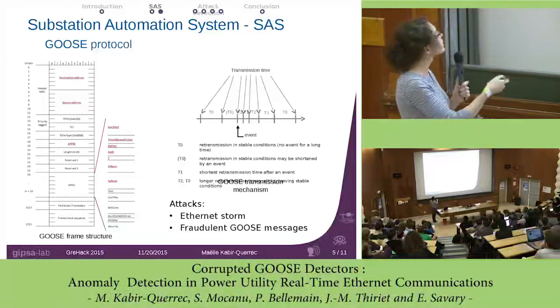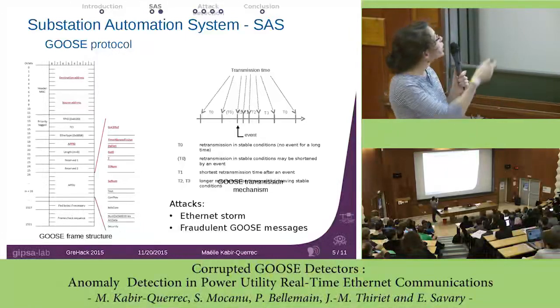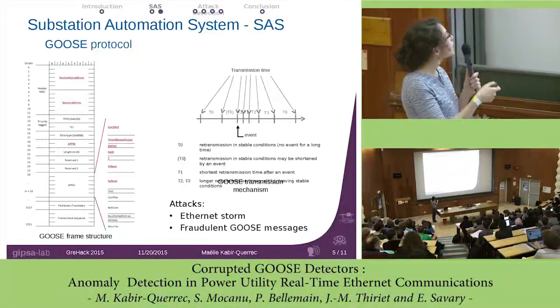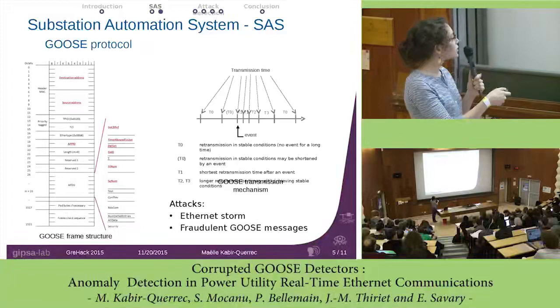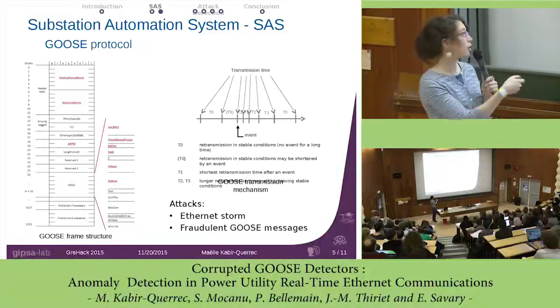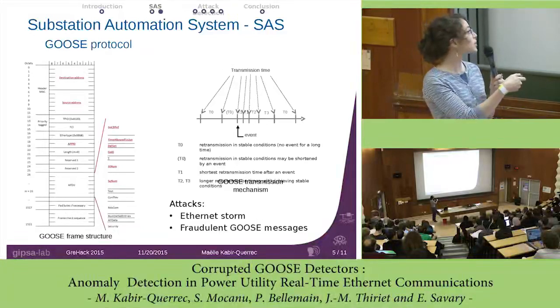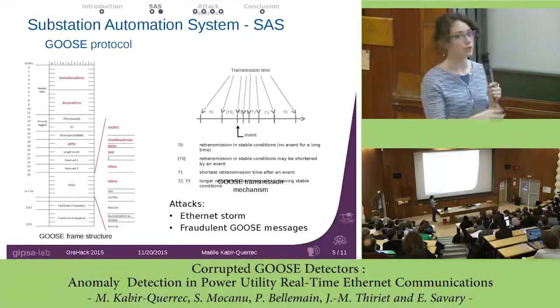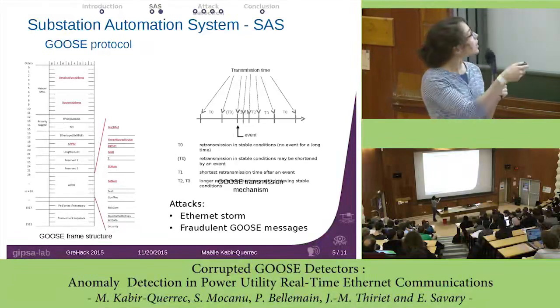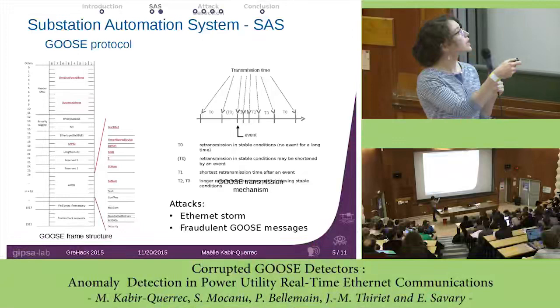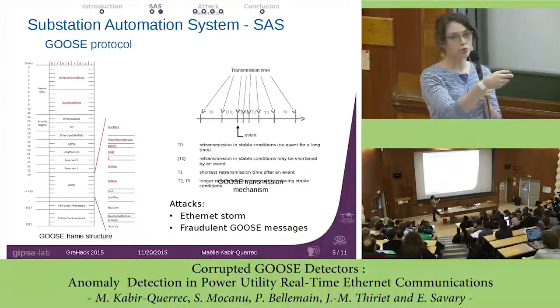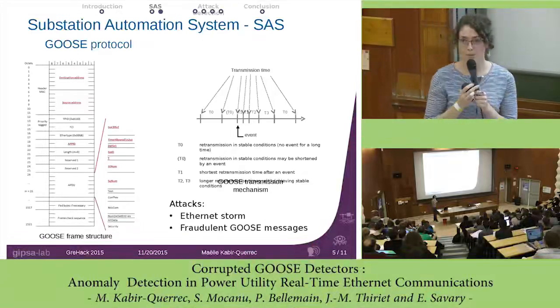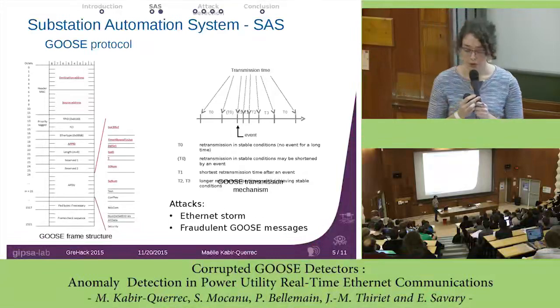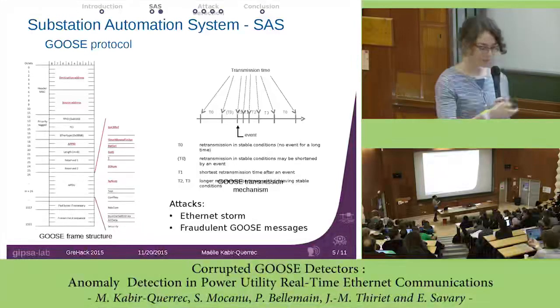So this is basically an Ethernet frame. You start your frame with destination address and source address. And the most interesting part is the PDU, the application protocol data unit of the frame. The fields that are interesting are the GOOSE control block reference, that is the name of the GOOSE message. It defines the transfer parameters.